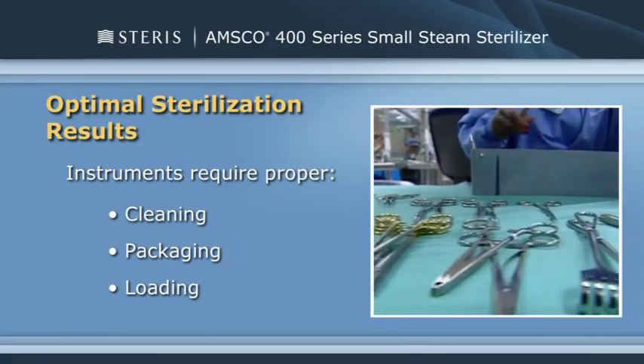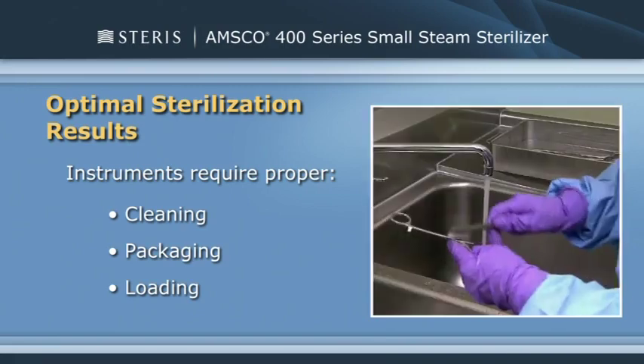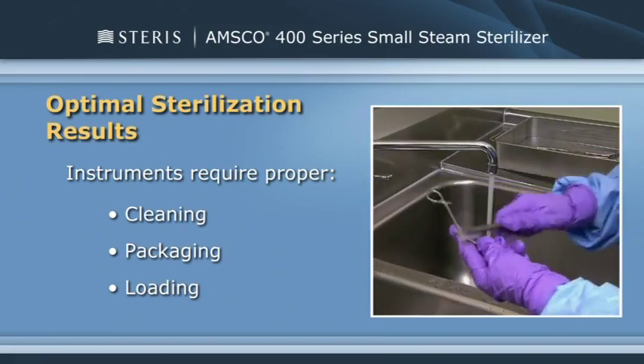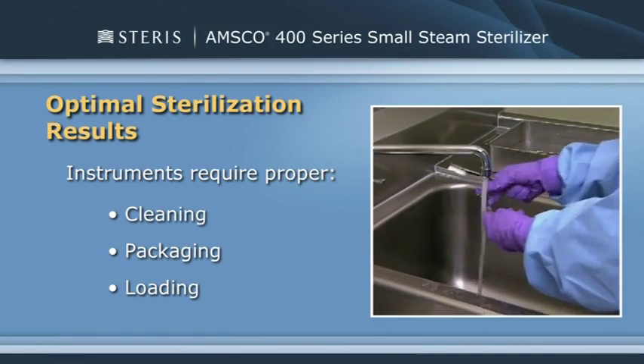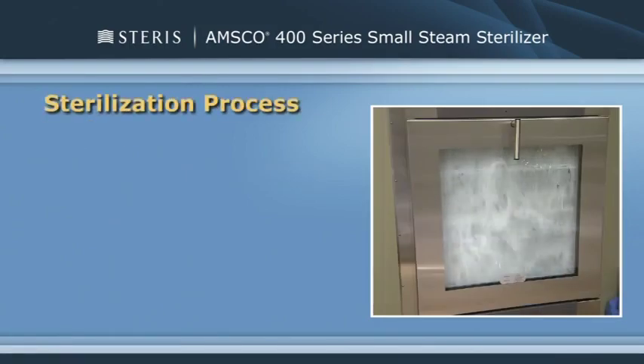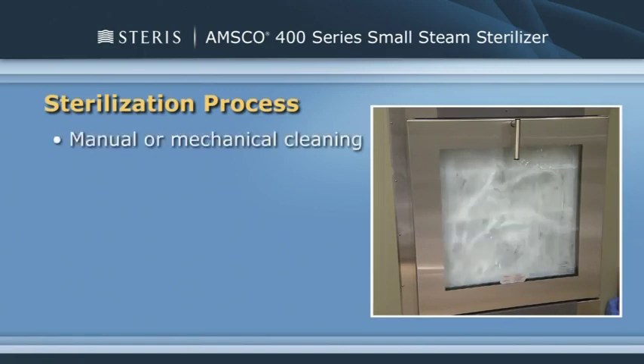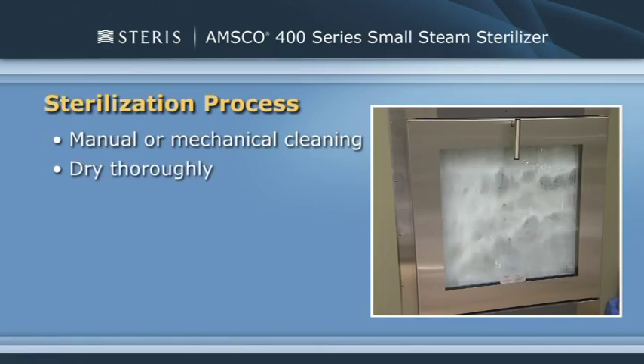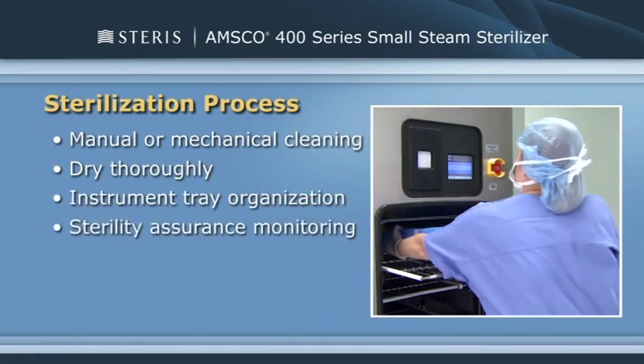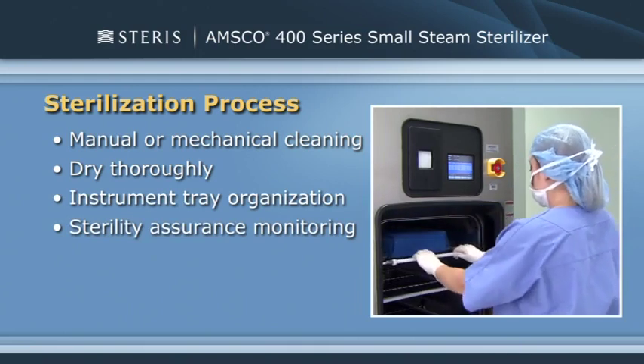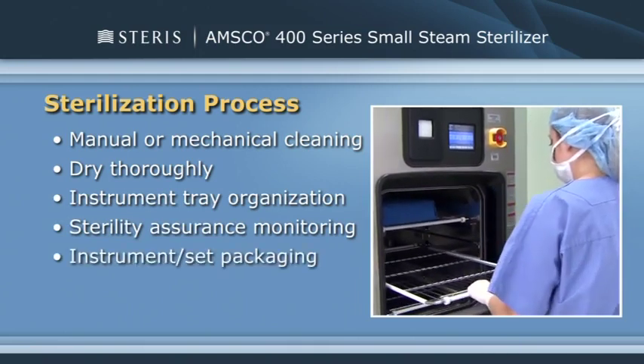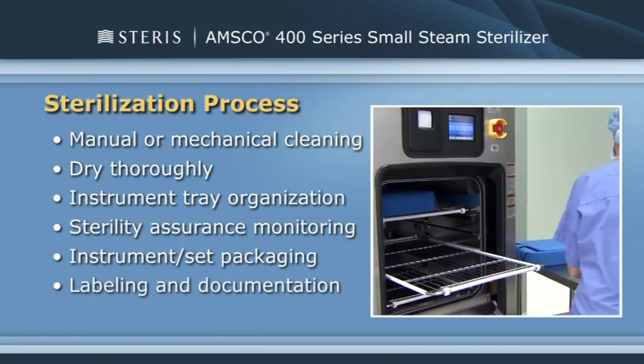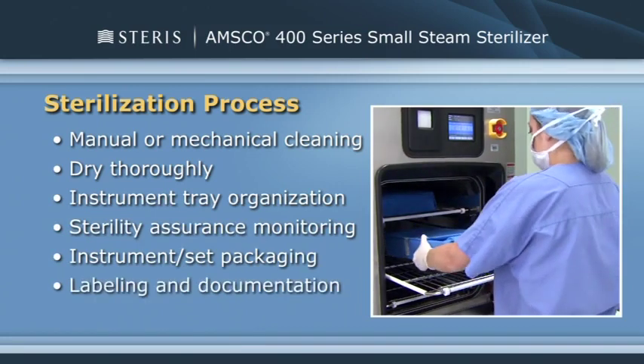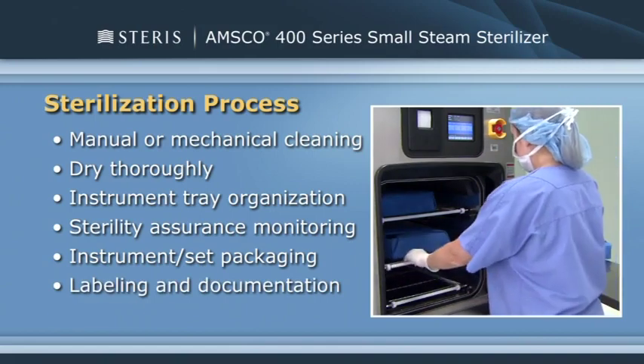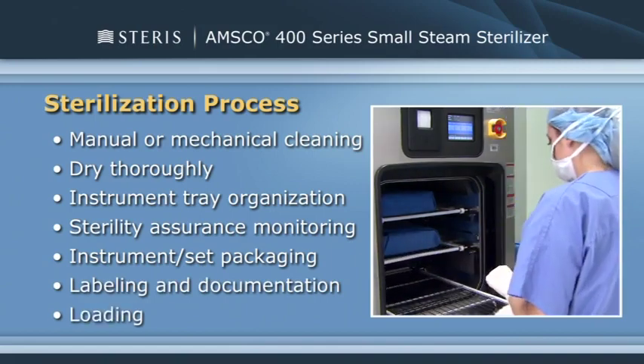Steam sterilization relies on steam reaching all instrument surfaces. Therefore, proper cleaning, packaging, and loading of the instruments are vital to achieve optimal sterilization results. The sterilization process includes these general steps: manually or mechanically clean instruments to remove visible soils, dry instruments thoroughly, organize instrument trays, include pack control sterility assurance monitoring chemical indicator, package instruments and instrument sets, label and document packages, include load control sterility assurance monitoring indicator, properly load the sterilizer.